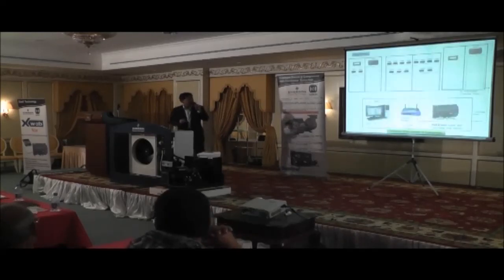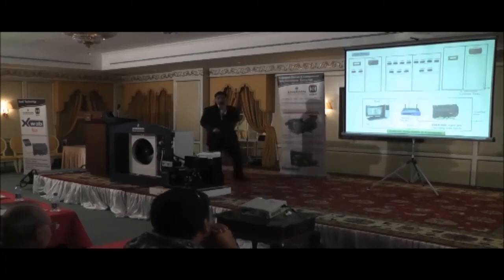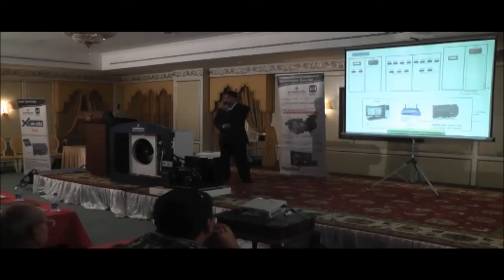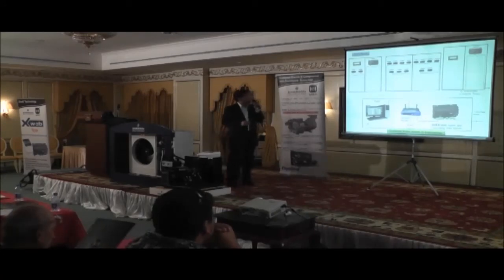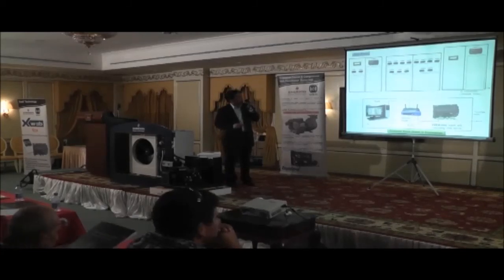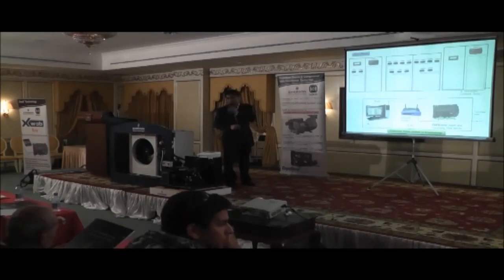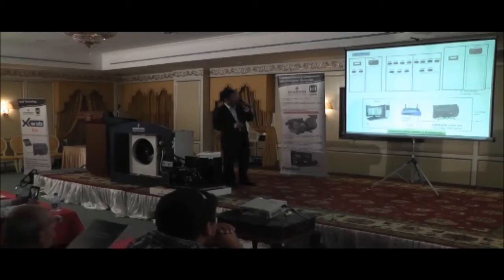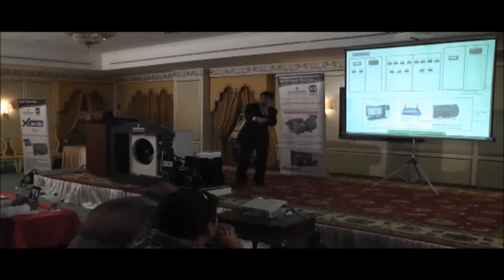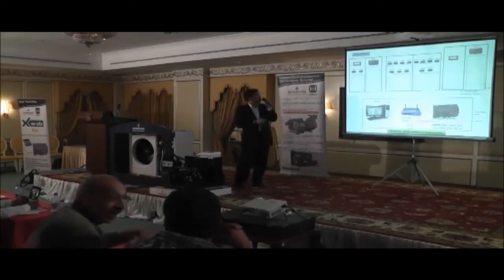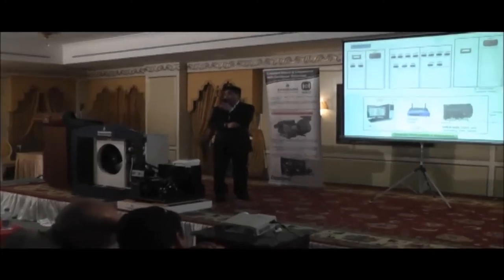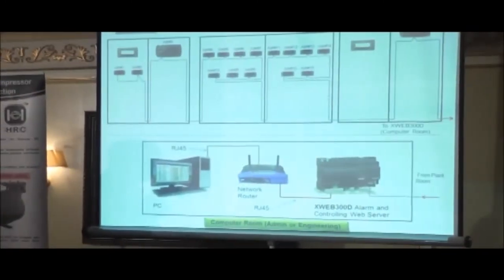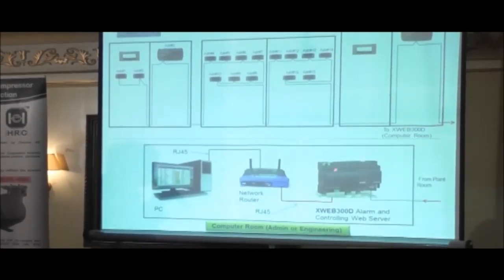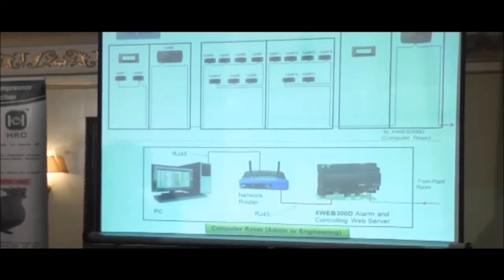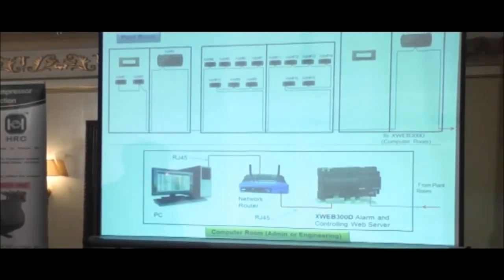This one is a typical setup we've done in Oman. This is an Almarai project in Oman. They have 13 cold rooms, a combination of freezer and chiller, and they have a rack compressor controller. These are the rack compressors for the chiller and for the freezer. We interconnected this via the RS485 network, from the plant room going to the computer room. In the computer room, they located the XWEB300D with the router and the computer.